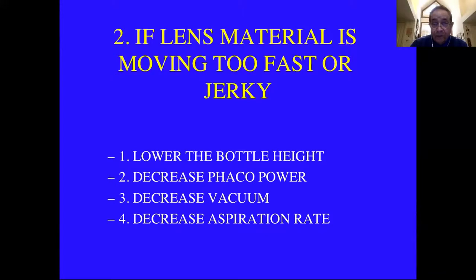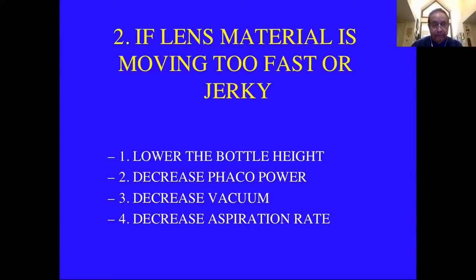Lowering the bottle would make it worse because you get less inflow. Phaco power wouldn't have any effect on how fast material moves. Decreasing the vacuum would have little or no effect. You have to decrease the aspiration rate if things are moving too fast.